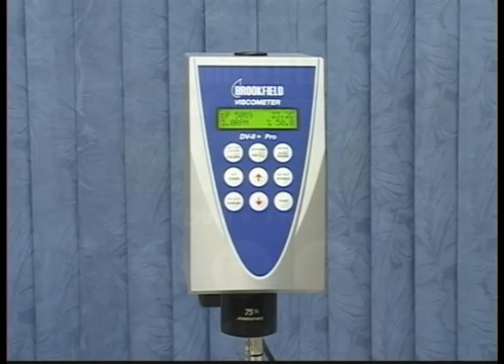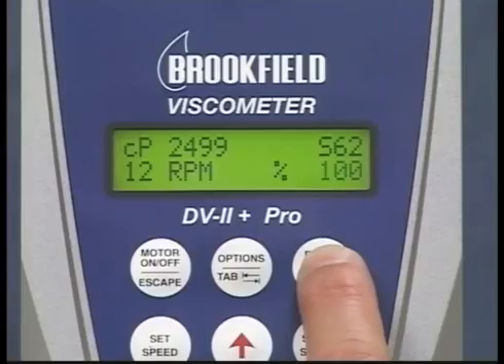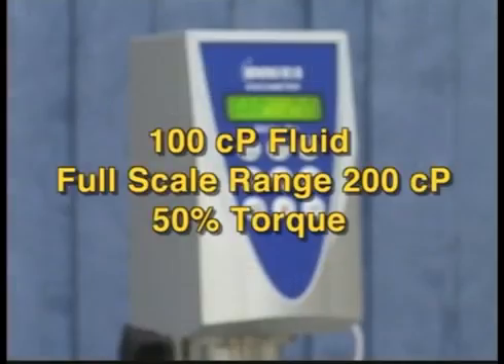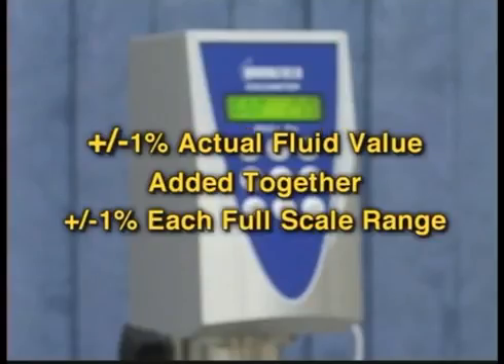With the digital instrument, you can easily find the full-scale range by turning on the motor and pressing and holding the auto range button. For example, if you have a 100 centipoise fluid, a full-scale range of 200 centipoise will give you 50% torque. Tolerances for calibration are computed using plus or minus 1% of the actual fluid value and plus or minus 1% for each full-scale range. Added together, this then gives you the tolerance for your reading.